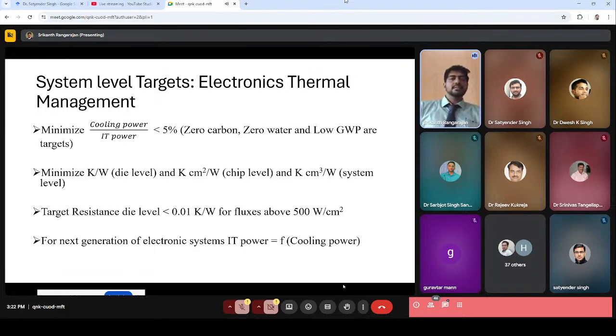So the system level targets for electronics thermal management are defined by the ARPA-E Cooler Chips program. As you can see here, the main objective is to minimize the ratio of cooling power to IT power to less than 5%, which is a very aggressive target. Today data centers operate anywhere between 30% to 40%, but now the new age target has to be 5%, meaning cooling power has to be less than 5% of the power consumed by the electronics.